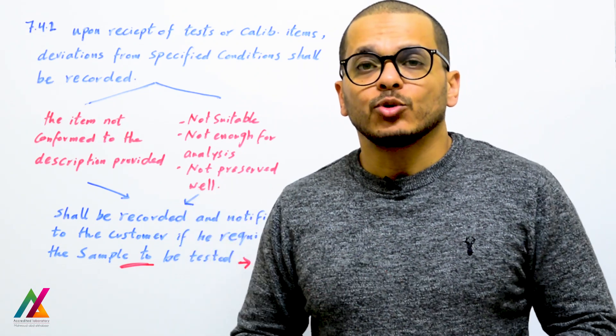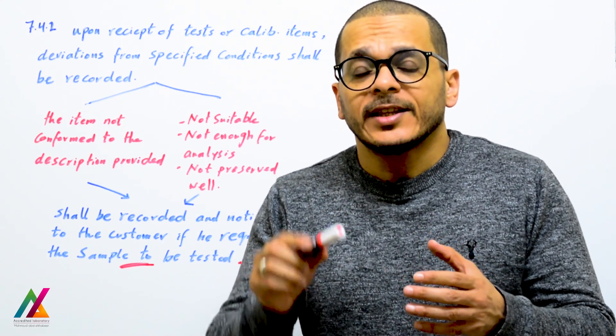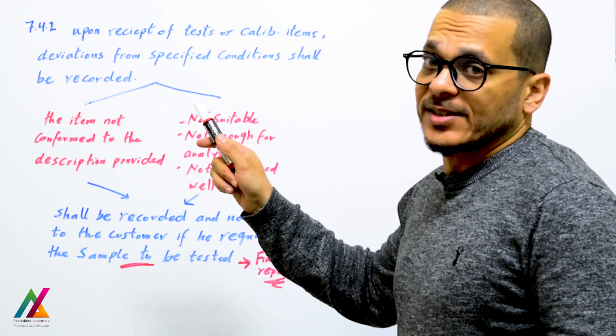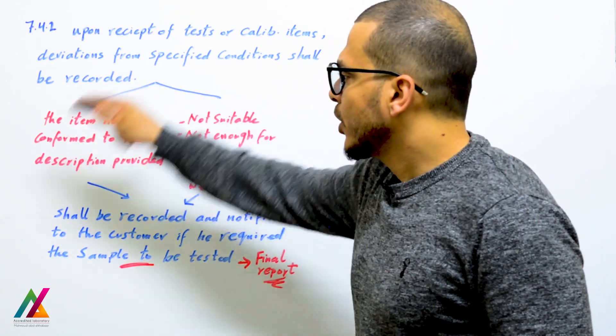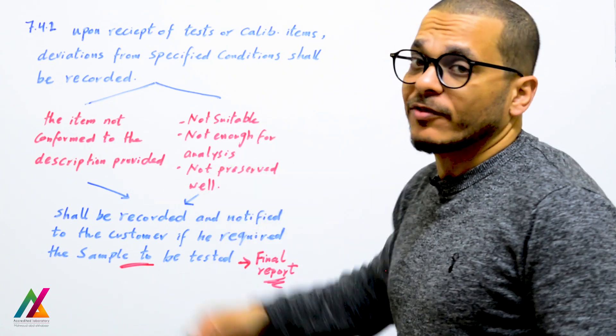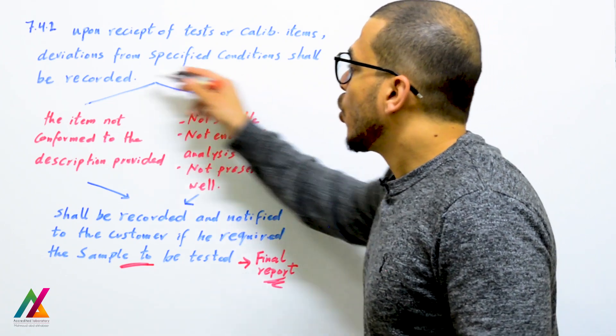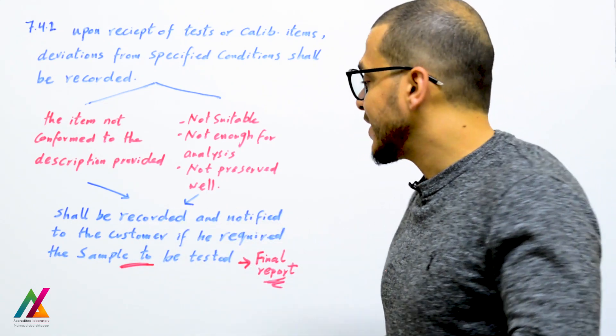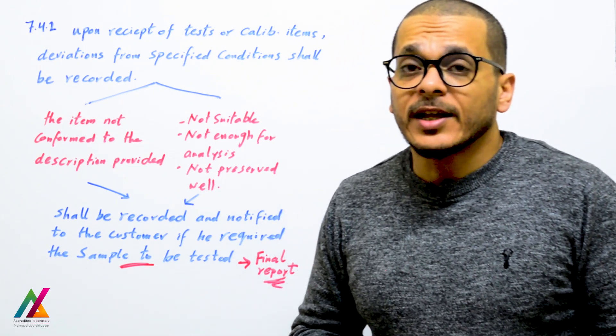Samples collected shall be checked at the lab to ensure their suitability for analysis. Upon receipt of test or calibration items, deviations from specified conditions shall be recorded — such as the item not conforming to its description, insufficient amount for analysis, or not properly preserved. All such deviations shall be recorded and the customer notified; if the customer insists on analysis, that shall also be mentioned in the final report.